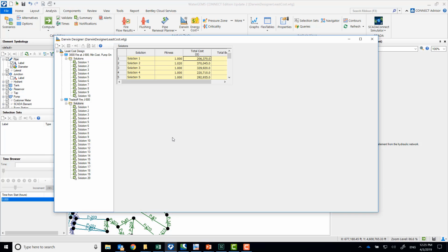So when you find one solution that you like, you then export it and then you see, okay, under these operating conditions, what's my pump going to be? What's the pump operation point going to be? Do I need to turn on another pump like you probably would in this case when your demands get to be so high? Most utilities would have kind of a jockey pump that only turns on when your demands go really high, like in this case of the fire.